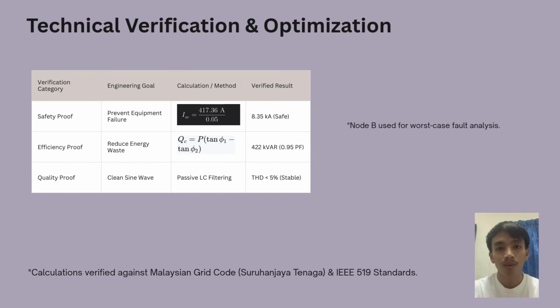As you can see in the power triangle, this significantly reduces the wasted reactive power, allowing our hydro generator to run cooler and last longer. Finally, our use of passive LC filters ensures that harmonic distortion from our power electronics stays below 5%, keeping the power quality clean for the community.